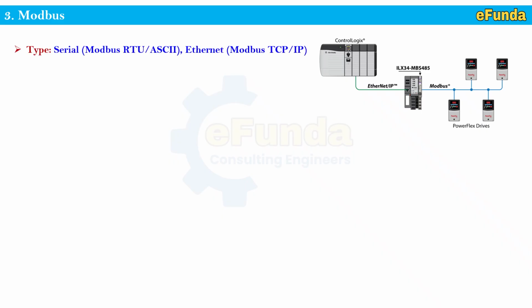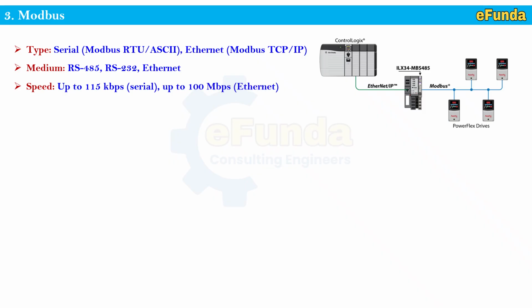One can refer to the type: serial Modbus RTU and ASCII, as well as Ethernet Modbus TCP/IP. Medium: RS485, RS232 and Ethernet. Speed: up to 115 kilobits per second for serial communication, and up to 100 Mbps through Ethernet communication. Topology: master-slave or client-server configuration.